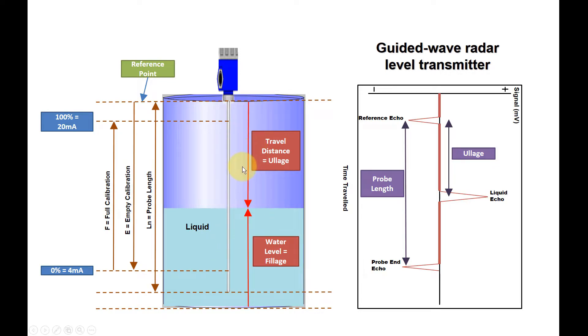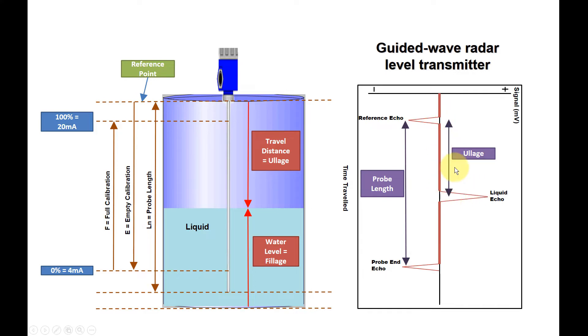This is the probe length — it's the length of the probe. This is a travel distance, or we call it ullage. Ullage is the distance from the reference point to the liquid surface. The opposite of ullage is water level, or sometimes we call it fillage — fillage is actually from the word 'filled with water,' measured from the bottom of the tank or vessel all the way to the water level. Between the reference echo and probe end echo is the probe length, and between the reference echo to the liquid echo is the ullage.